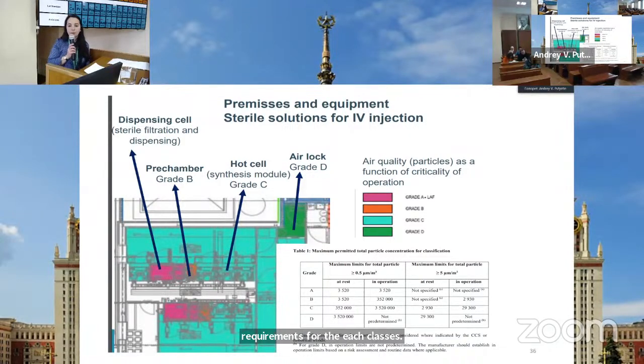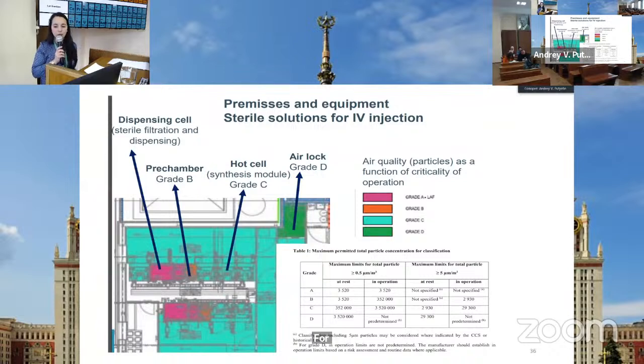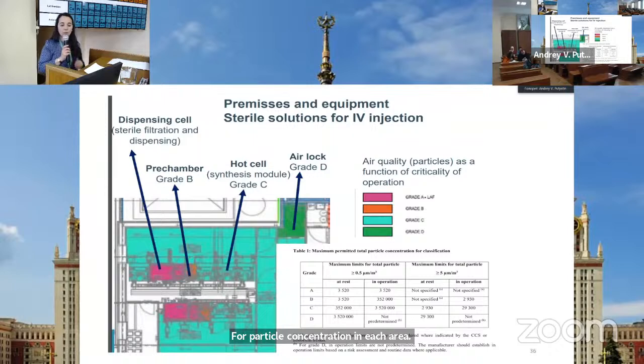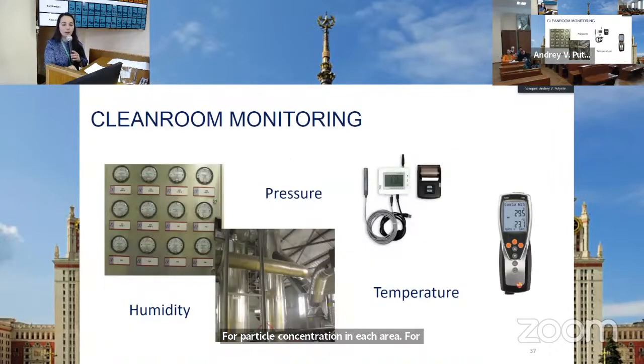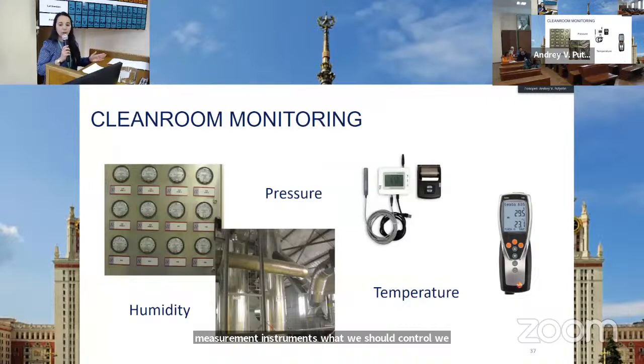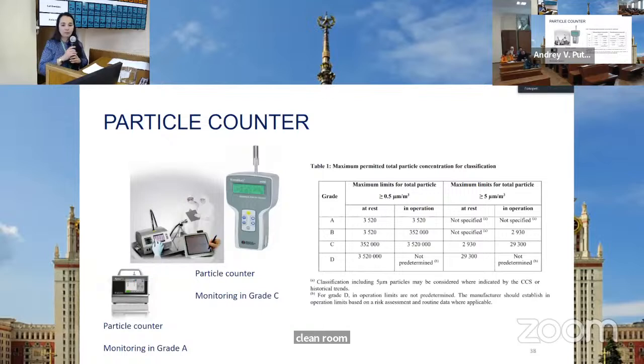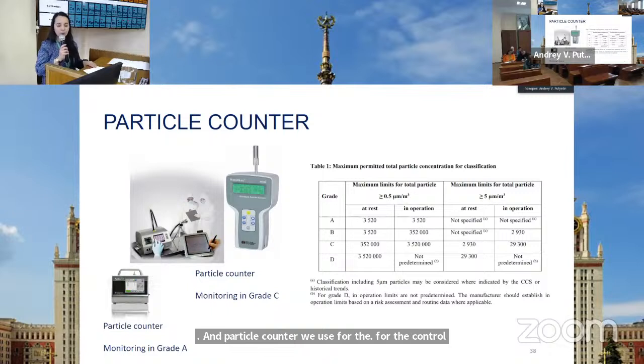For particle concentration in each area, for classification of each type of clean room. How do we control it? We can control and monitor our clean rooms with different measurement instruments. What should we control? We should control pressure inside the clean rooms and clean room area, humidity, temperature, and we use a particle counter for the control of concentration of particles inside each area.